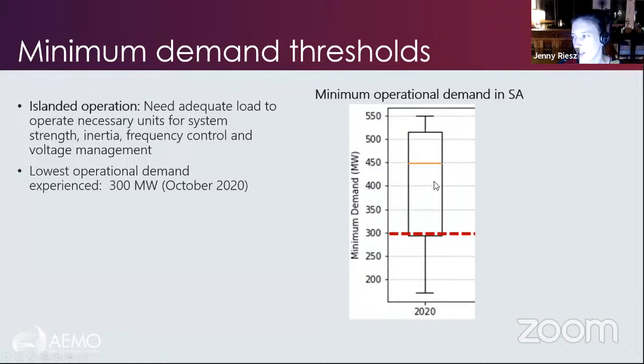But as load starts falling into this range, we're losing combinations of units. So we're losing flexibility in how we dispatch that system. And that's making it increasingly difficult, particularly when there's unit outages for maintenance or line outages or other constraints. The minimum that we've measured in South Australia most recently in spring was around 300 megawatts of demand. So we're very well down in the range where we have only a very small number of unit combinations that we can run now if we island that part of the grid in a high PV period.